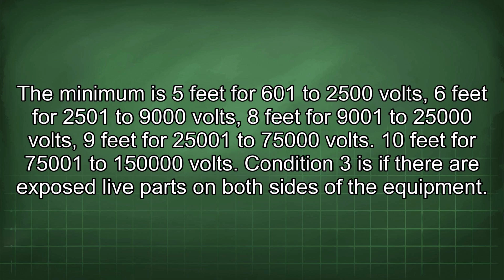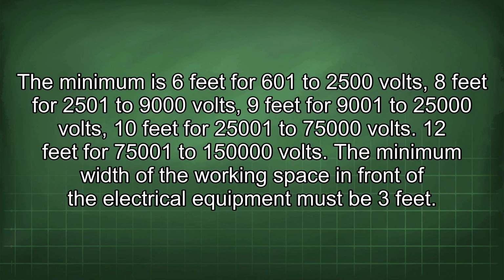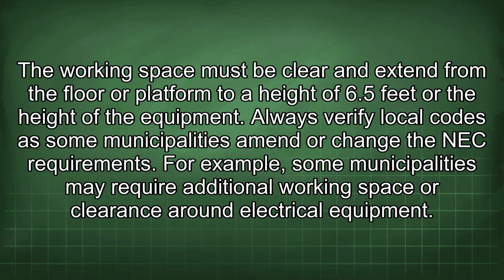Condition 3 is if there are exposed live parts on both sides of the equipment. The minimum is 6 feet for 601 to 2500 volts, 8 feet for 2501 to 9000 volts, 9 feet for 9001 to 25,000 volts, 10 feet for 25,001 to 75,000 volts, 12 feet for 75,001 to 150,000 volts. The minimum width of the working space in front of the electrical equipment must be 3 feet. The working space must be clear and extend from the floor or platform to a height of 6.5 feet or the height of the equipment.